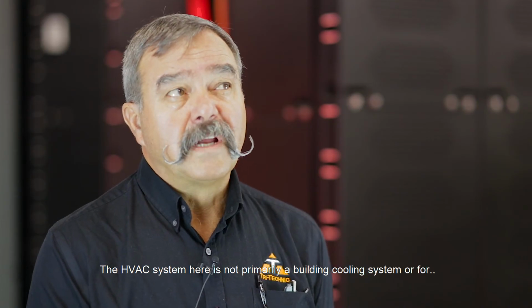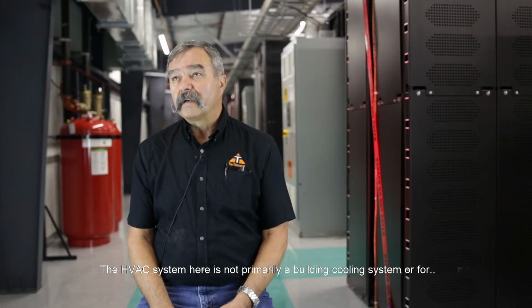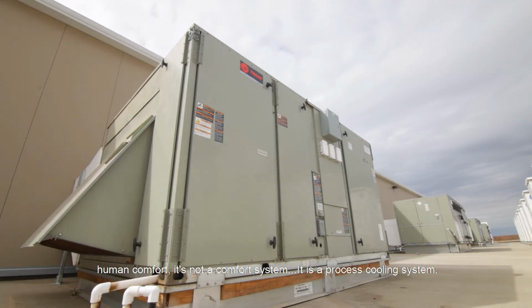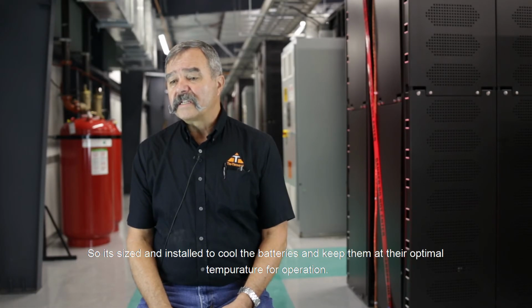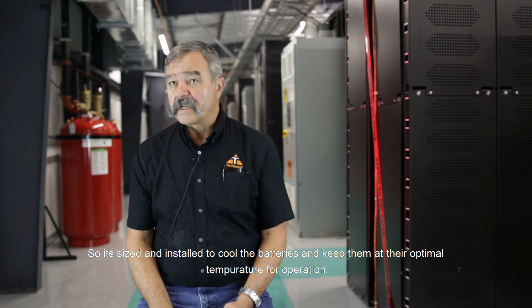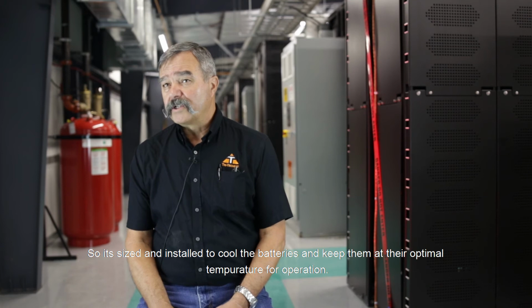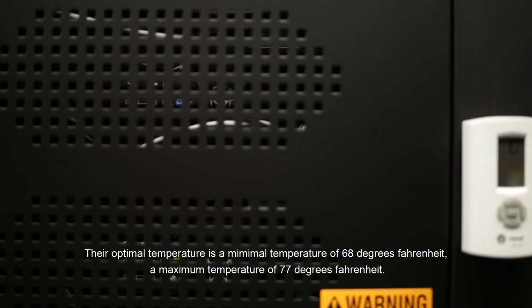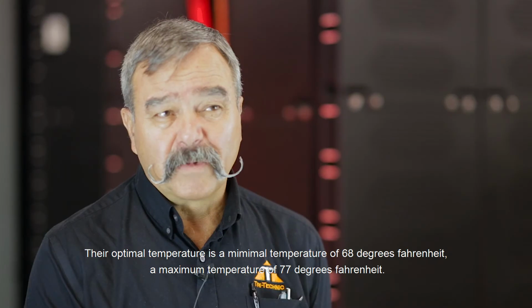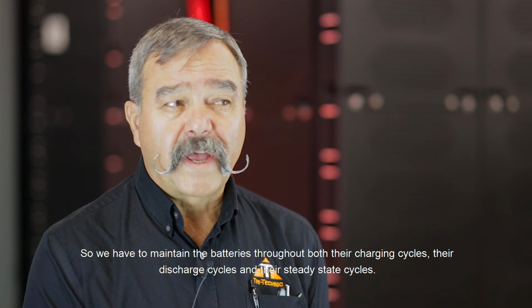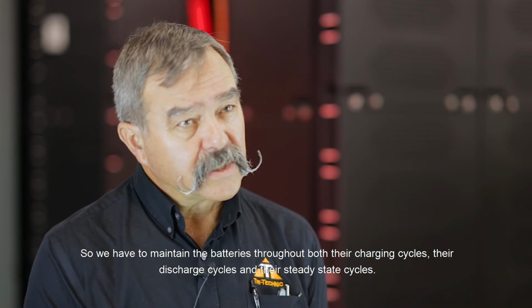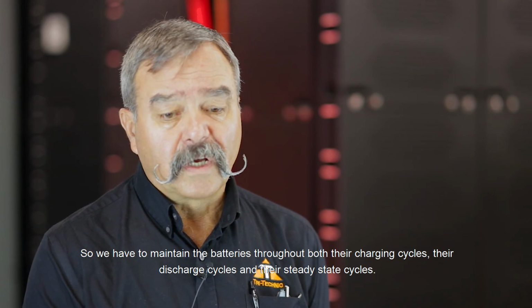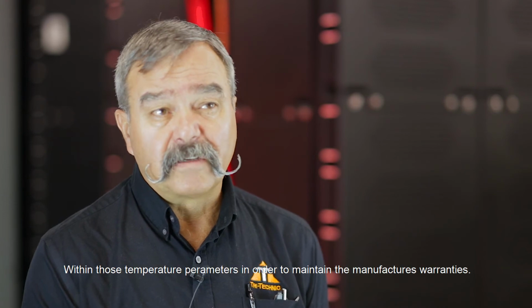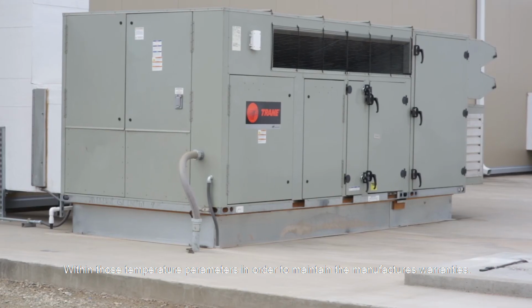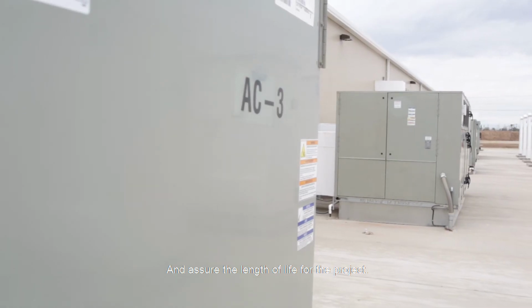The HVAC system here is not primarily a building cooling system, or for human comfort. It's not a comfort system. It is a process cooling system. So it's sized and installed to cool batteries and keep them at their optimal temperature for operation. Their optimal temperature is a minimum of 68 degrees Fahrenheit and a maximum of 77 degrees Fahrenheit. We have to maintain the batteries throughout their charging cycles, their discharge cycles, and their steady state cycles within those temperature parameters in order to maintain the manufacturer's warranties and assure the length of life for the project.